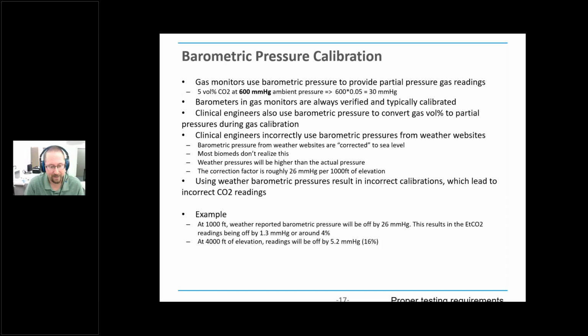So for example, if you're at 1,000 feet, you're off by about 4%. By the time you get to 4,000 feet, you're off by 16%. So if you're at sea level, you're probably okay. Still would be better to have an absolute gauge, but if you're not at sea level, you should definitely be using some kind of gauge in your shop to determine that.